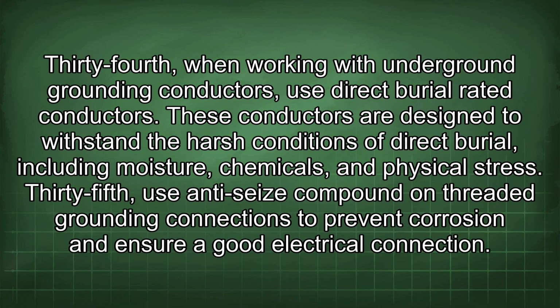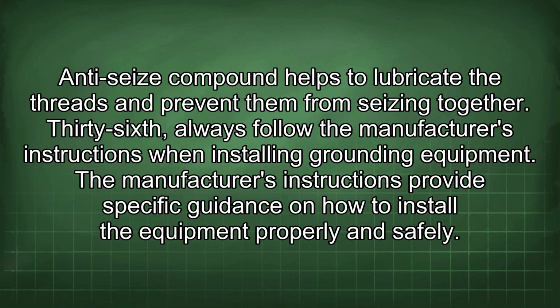34th. When working with underground grounding conductors, use direct burial rated conductors. These conductors are designed to withstand the harsh conditions of direct burial, including moisture, chemicals, and physical stress. 35th. Use anti-seize compound on threaded grounding connections to prevent corrosion and ensure a good electrical connection. Anti-seize compound helps to lubricate the threads and prevent them from seizing together.